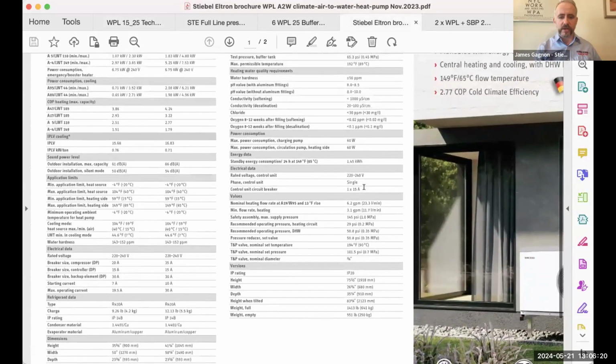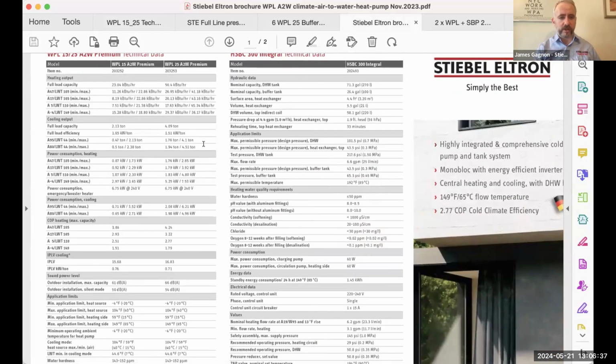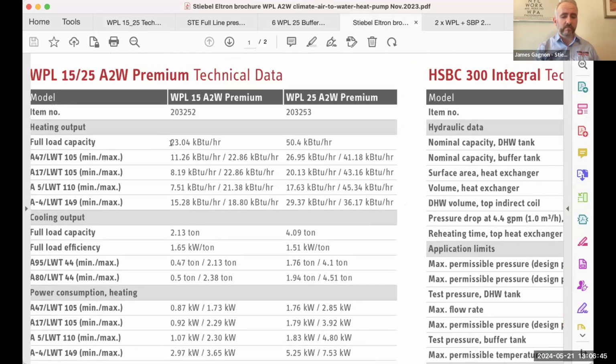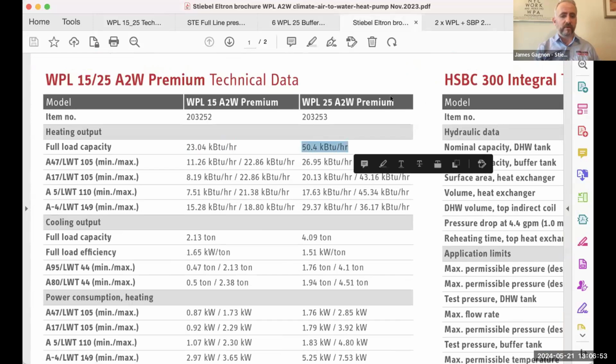So the Sandon unit is a CO2 based water heater unit. It is an interesting product. It is a water heating unit. It pretty much has very little to zero heating capacity, and each of those individual outdoor units is, I think, around 13 to 15K BTU per hour. Our small one is 23K BTU per hour, and our 4-ton unit is like 50K BTU per hour. So 3 times as strong in an outdoor unit that's a little bit bigger, but it's still just one outdoor unit that can do very high outflow temperatures for actual real heating and water heating and can do cooling. Our air to water heat pumps without CO2 can do cooling. The Sandon unit is pretty much just a water heating unit.